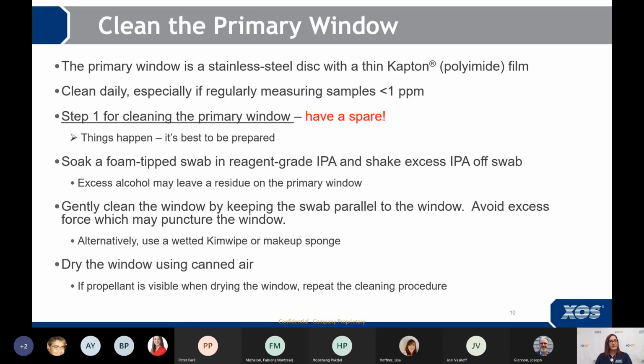So the primary window is a stainless steel disc with a thin Kapton® (polyimide) film. And we actually recommend you clean this daily if you're regularly running samples that are less than 1 ppm. If you're not, I would still recommend that you at least check it daily to make sure that there's no contamination on the window. Now, the very first step when cleaning the primary window is to have a spare window handy, okay? You want to have this spare window handy because accidents happen, and you wouldn't want to be down because as you were cleaning the window with a swab here, you accidentally punctured a hole in it. So make sure you have a spare.